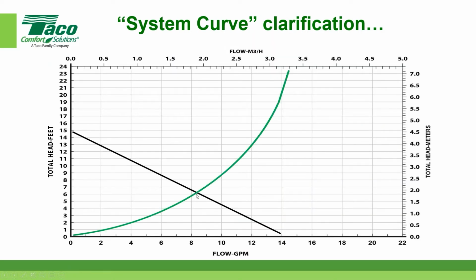And I want to show you, if I had all the zones open, what happens on a multi-zone system when you actually start closing valves, like zone valves. If a valve was to close, the curve kicks its way up. Notice how it moves from the right and up to the left. If another valve closed, you're going to get kind of the same thing here. And I want you to understand, here's the circulator performance curve. How does the system curve interact with that? If it's running at maximum speed, it's going to do the same thing I just showed you, up and to the left.